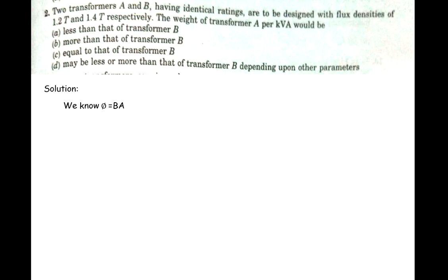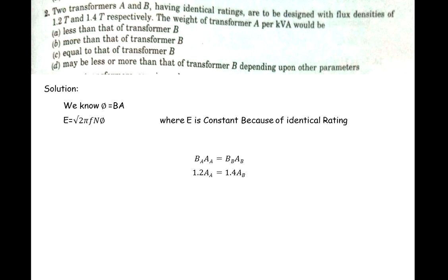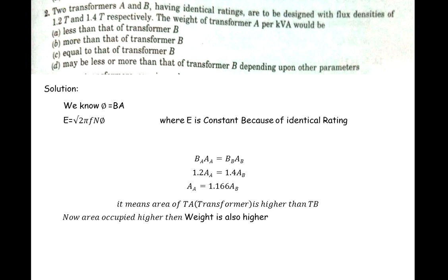We know that flux φ = B·A, and EMF E = √2·π·f·N·φ. Since E is constant due to identical ratings, we get B_A·A_A = B_B·A_B. After putting in the flux density values, the area of transformer A is greater — about 16.6% more than transformer B. Since the area is higher, the weight is also higher. Therefore, the weight of transformer A per KVA would be more than that of transformer B, so Option B is correct.